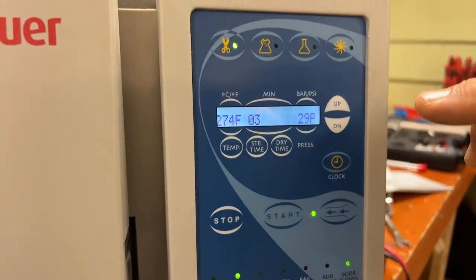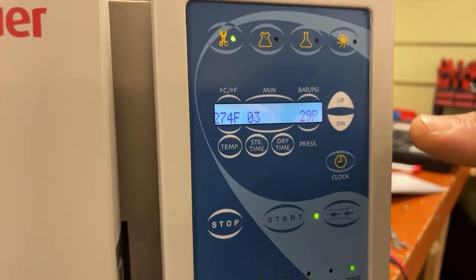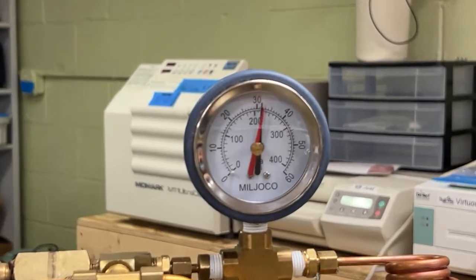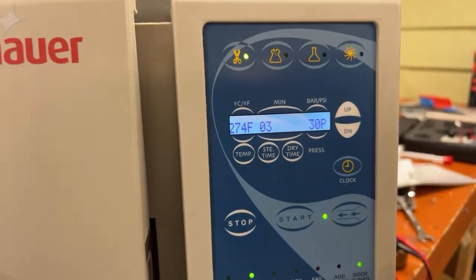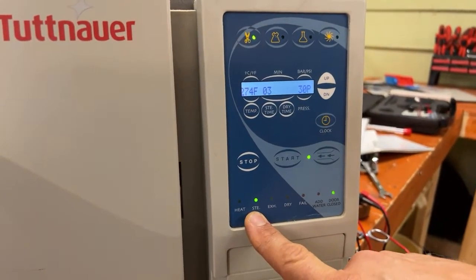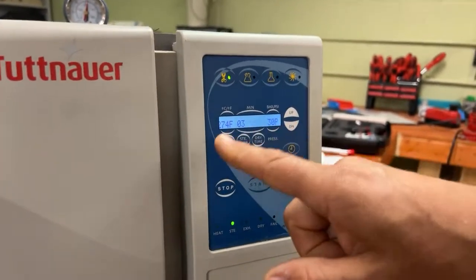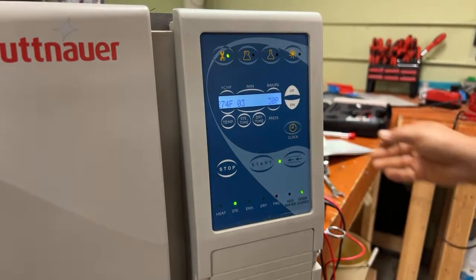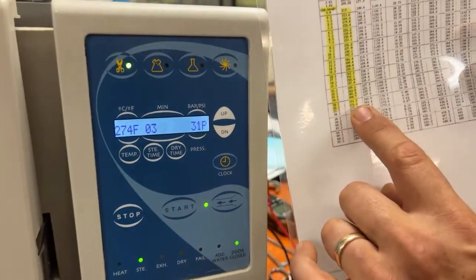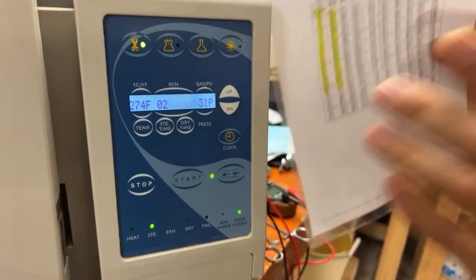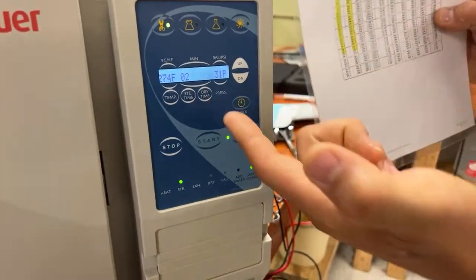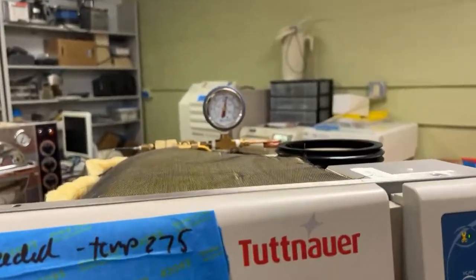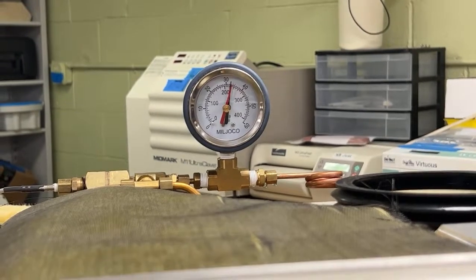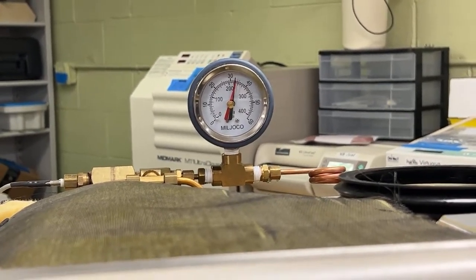Okay, so here we are. Right now we're at 29 pounds of pressure. We are at 274 degrees. Now 30 pounds of pressure, and we're set at 273. We're at 30. It should click over. It actually is sterilizing right now. Looking at this, those two numbers to me are very healthy. 30 pounds of pressure is great. Let's look at our saturated steam chart just to double check. So 30, 274. No, that's perfect. And that's why this chart is important, because the chart tells you everything's okay. Now, we are maybe running a little high on the pressure side, but we'll see what happens here.